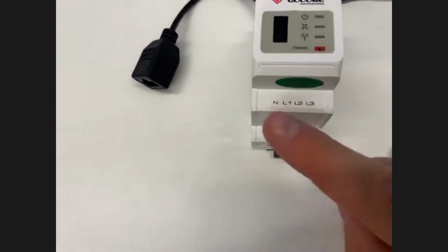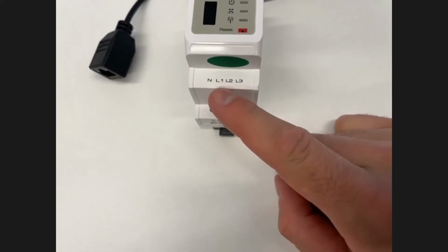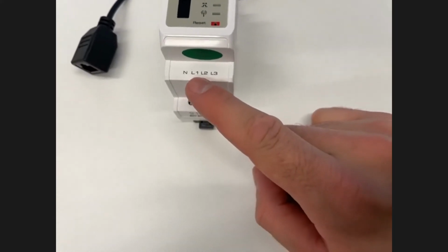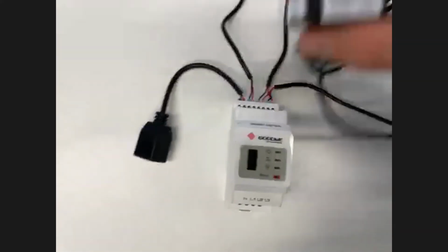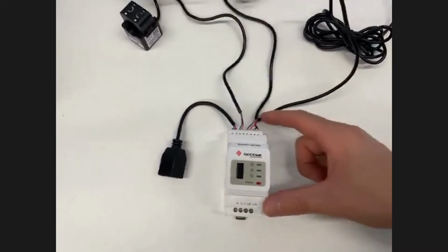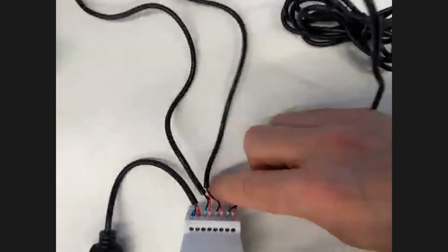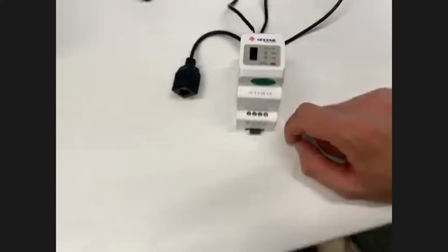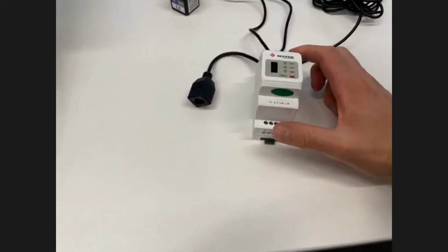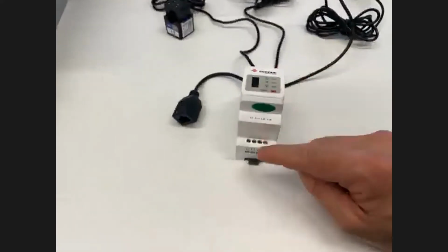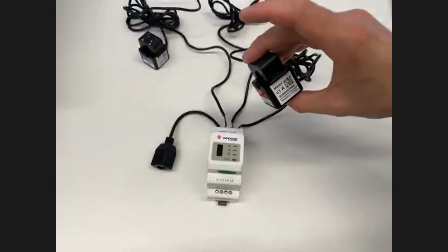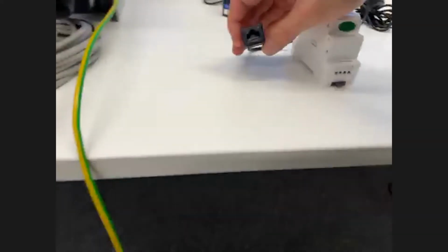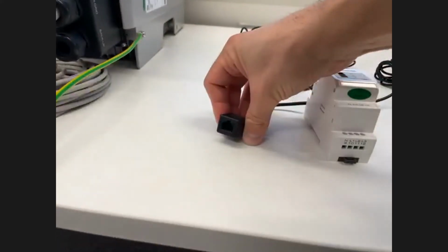On the bottom side, the first line goes from left to right instead, compared to on top where CT A is connected on the right side. But basically everything is already pre-wired. Make sure you connect these and attach the CTs correctly, then connect to this socket here, let's see if I can show you.